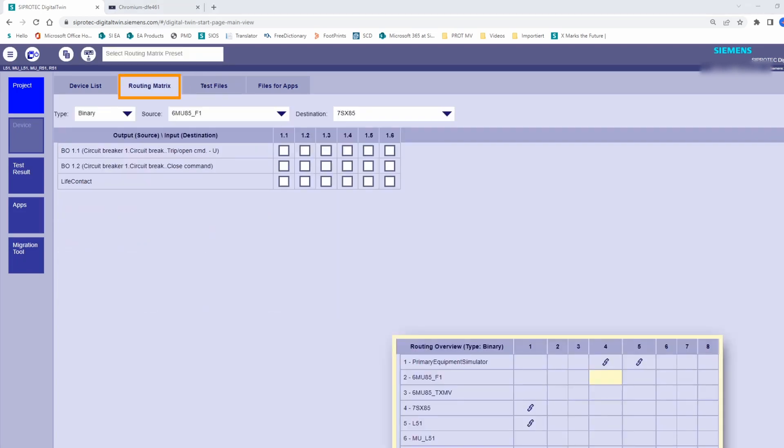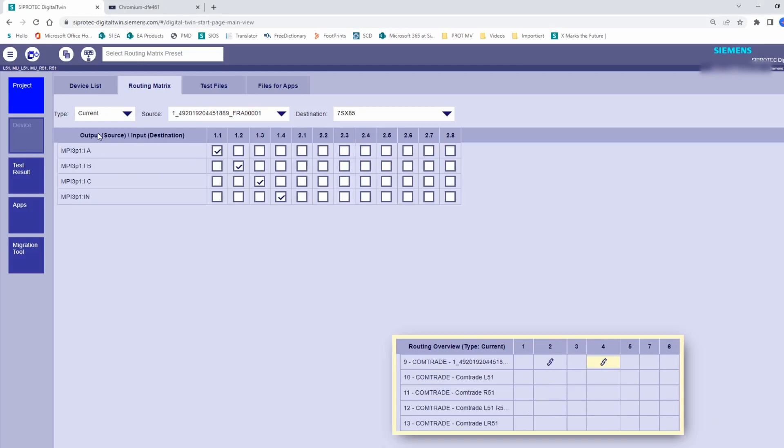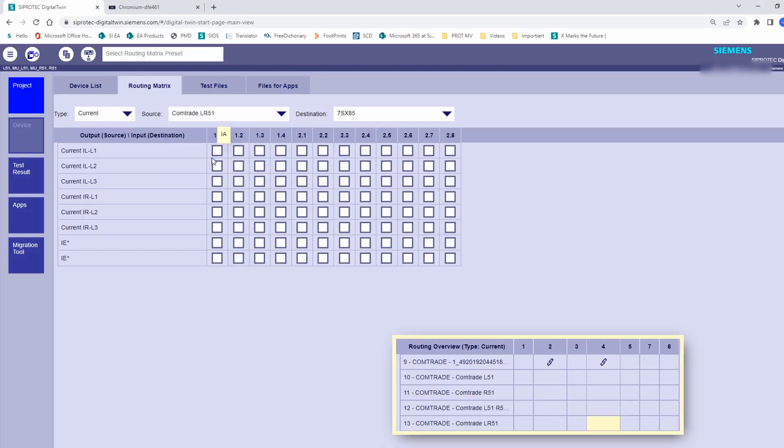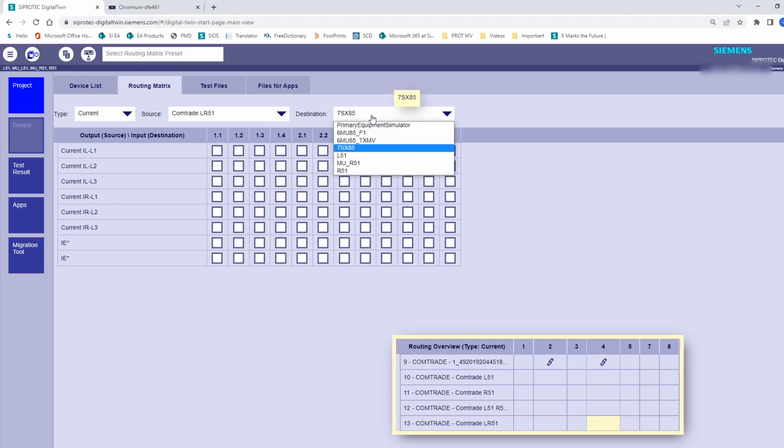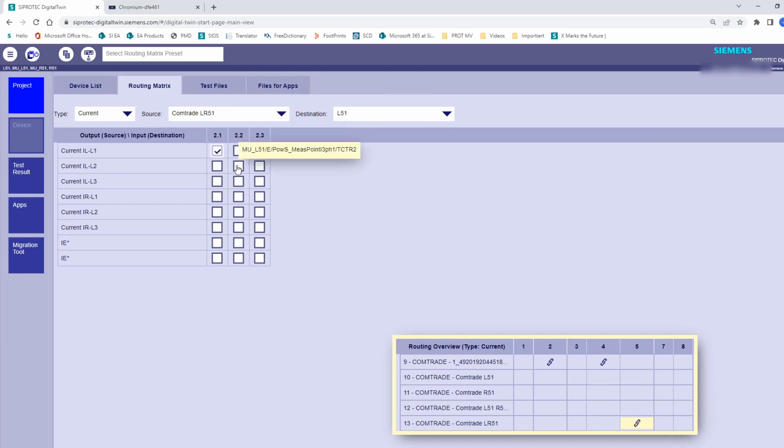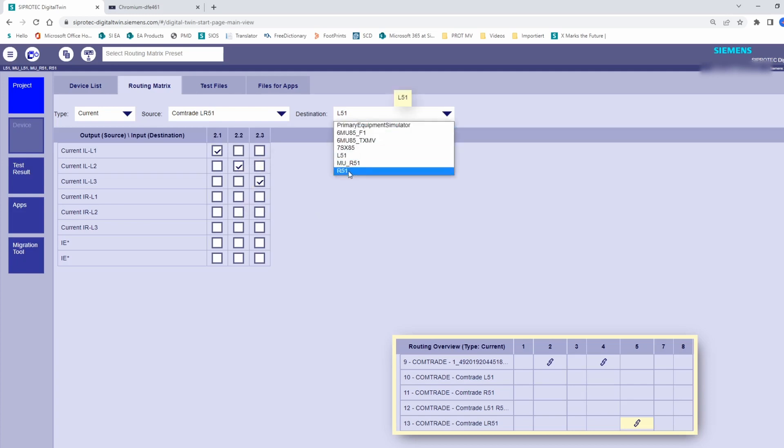And for that, we go to the Matrix Routing. We select, for example, Current, then we select as source our COMTRADE and as destination, our protection devices. We do it one by one. We start with the device of the left side. Assign the phase 1, the phase 2, and the phase 3, from the corresponding signals from the COMTRADE.